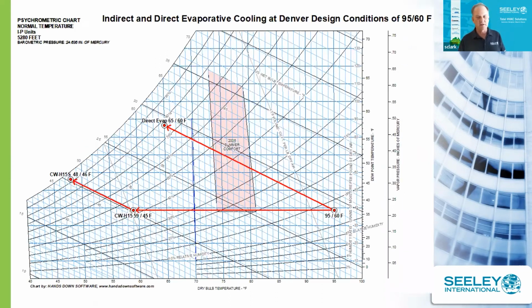I'm first going to start out, I know it's kind of early in the morning, with psychrometrics, but we're going to dive right into this. If we look at a psychrometric chart using the Denver design conditions of 95/60, we first look at direct evaporative cooling, or swamp coolers. And we start at this 95/60, we follow the wet bulb line up to about 65 degrees, 80% relative humidity.